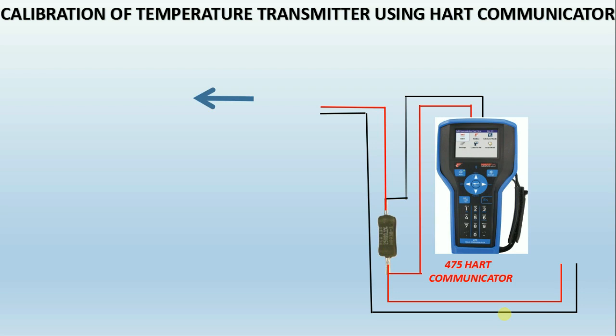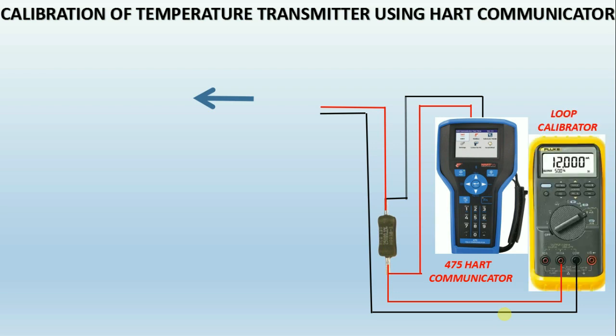What is a loop calibrator? For process calibration professionals, loop calibrators are essential tools for working with 4 to 20 milliamp current loops. Process control loop calibrators provide milliamp sourcing, simulation, and measurement, with readouts in both milliamps and percent of span, and a 24-volt loop supply.